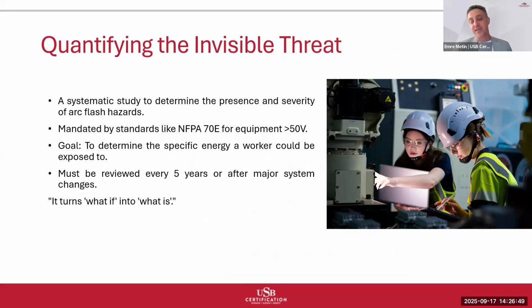Let me expand on what arc flash analysis actually involves, because understanding the process helps you evaluate the quality and reliability of the results. An arc flash analysis is fundamentally a systematic study to determine both the presence and severity of arc flash hazard throughout your electrical system. It's mandated by standards like NFPA 70E for equipment operating above 50 volts, but the real goal is practical: to determine the specific energy level a worker could be exposed to during an arc flash event at any given location. In the European Union, we have a similar standard, EN 50110. We call it the EN standard. These analyses must be updated every 5 years or after major system changes.